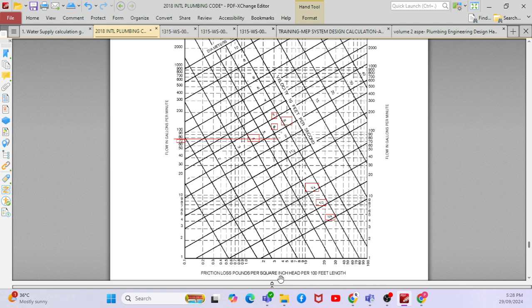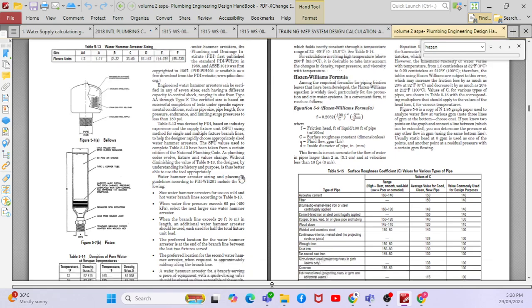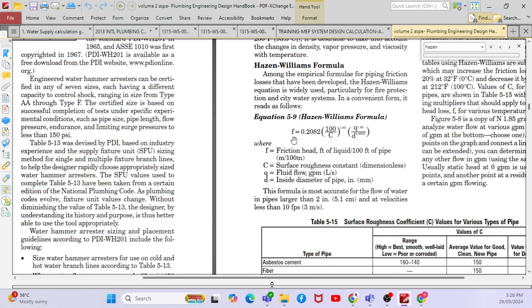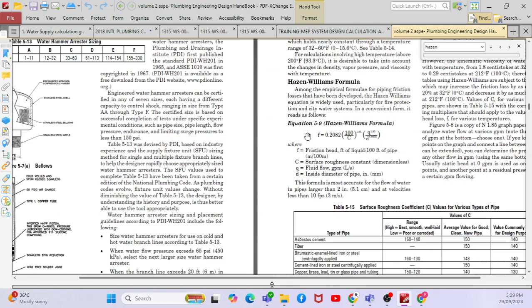Now, how does this pressure drop value come? It is based on two equations. One is the Hazen-Williams equation: F = 0.2082 × (100/C)^1.85 × Q^1.85 / D^4.865. Using this equation you can calculate friction head in feet of liquid per 100 feet of pipe. There are different equations for different units — you can calculate in feet, PSI, meters, or bar. This is the Hazen-Williams formula.